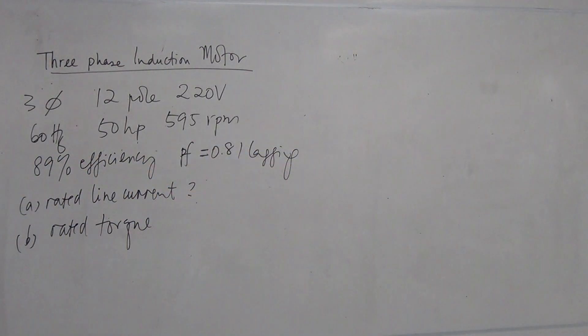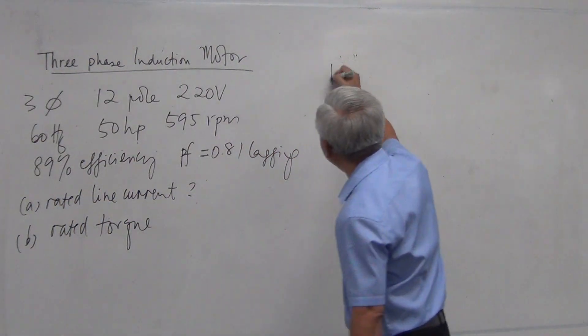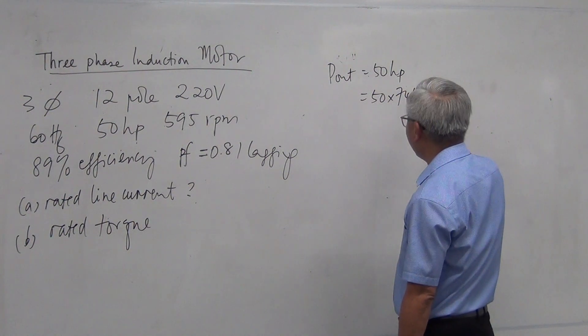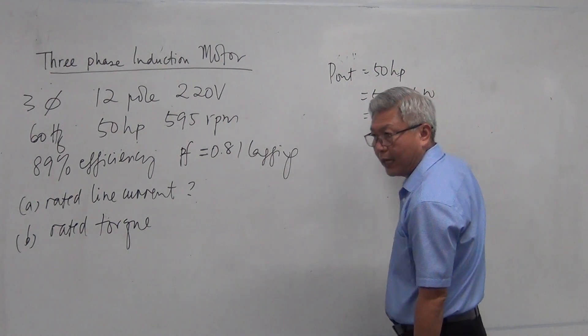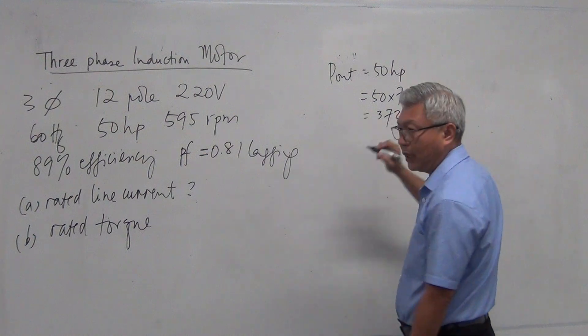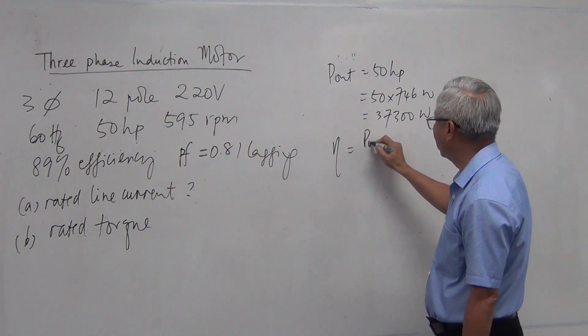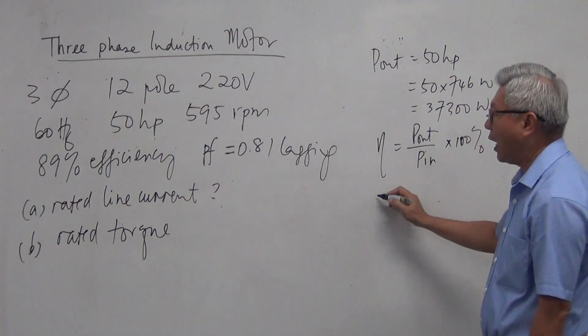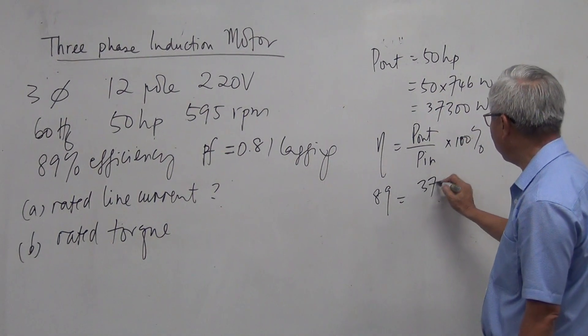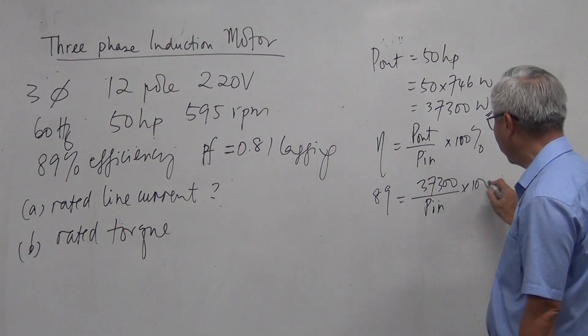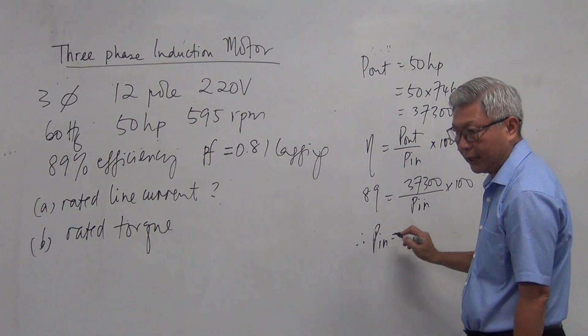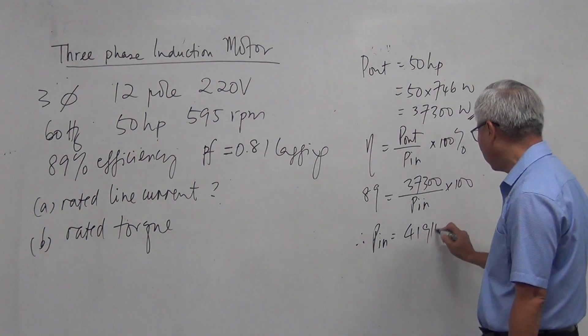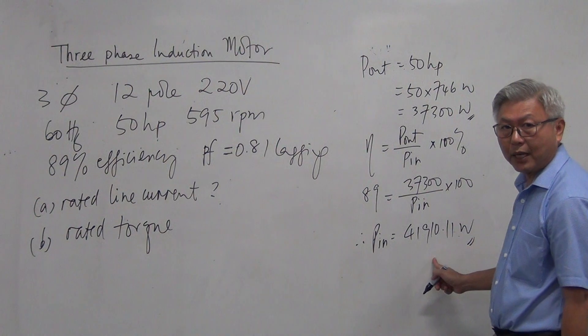Alright. Start with the efficiency first. So, the output power is equal to 50 horsepower. Make it into SI unit times 746 watts. And that is equal to 37,300 watts. And efficiency, efficiency is output divided by input times 100%. So I have 89 percent, that is equal to 37,300 watts divided by input power multiply 100. So therefore, input power can be calculated. And input power is equal to 41,910.11 watts. So I've already got my input power.